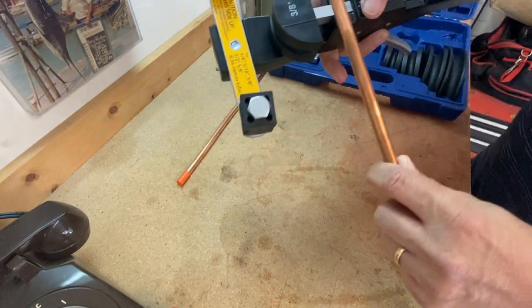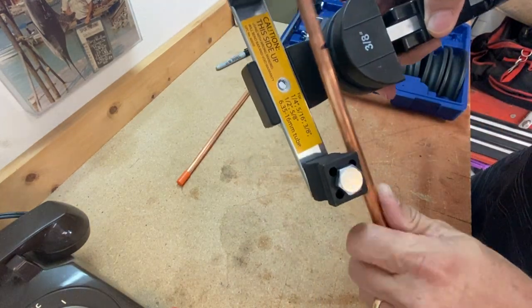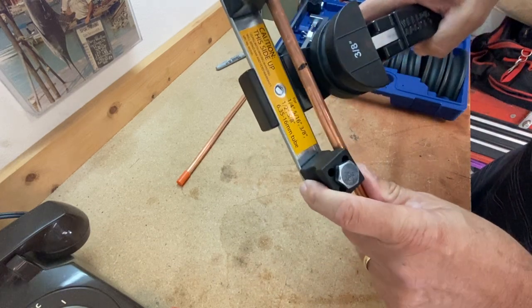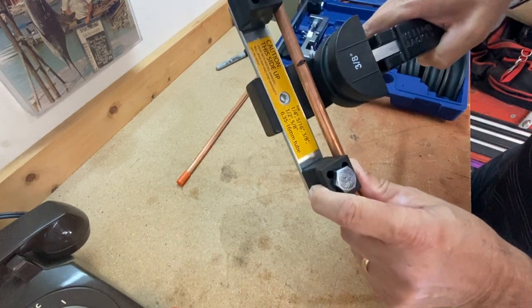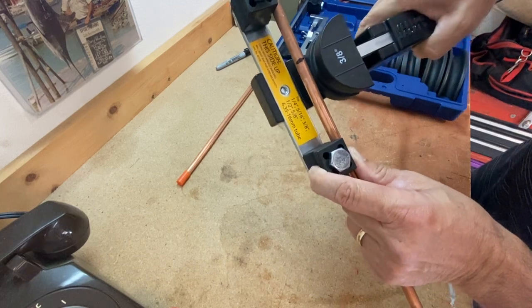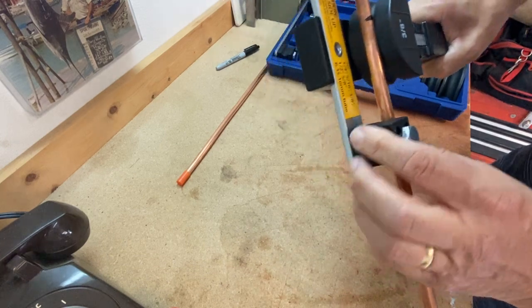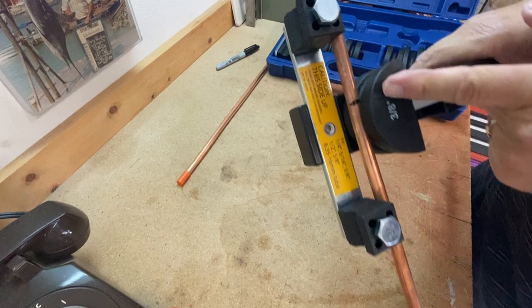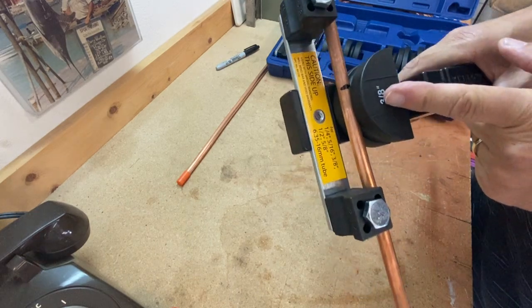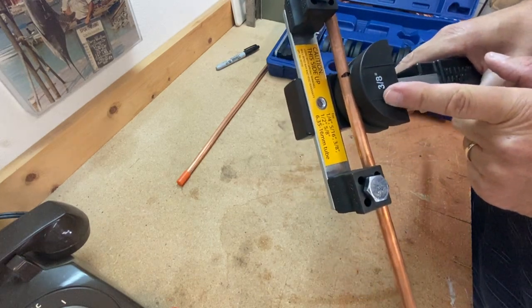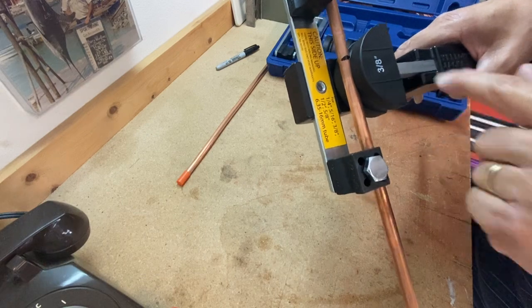I line up the mark I put on my tubing with the right side. So I want the top of my bend to be lined up with the index mark. If I wanted the bend to be at the bottom, I would put it at the other index.